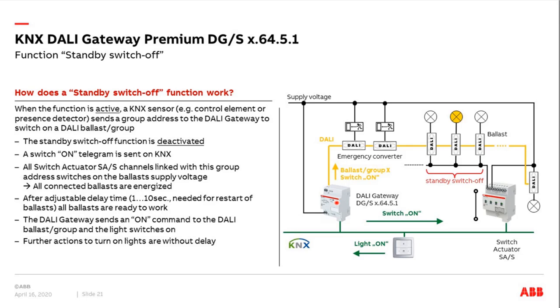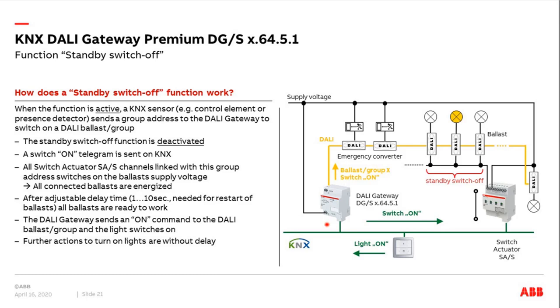After this delay time, when all ballasts are ready, the DALI gateway sends the command into the DALI world to switch on the selected ballast or group, and the light goes on. We have only a short time delay — for example, one second between pressing the KNX button and the light switching on. This is a minimum of one second and a maximum of ten seconds.